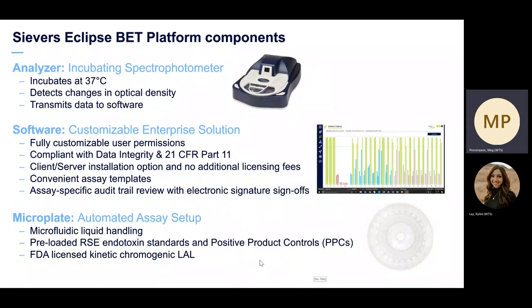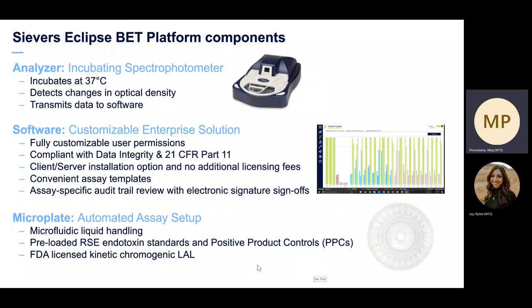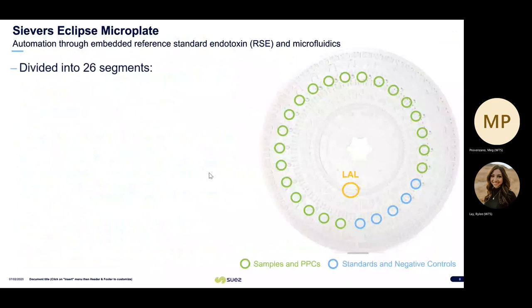There are also convenient assay templates. The microplate is a microfluidic liquid handling plate pre-loaded with RSE endotoxin standards and positive product controls. It can also use the FDA-licensed kinetic chromogenic LAL. The microplate allows for precise measurement, distribution, and mixing of samples, standards, and LAL. There's a one-to-one sample-to-lysate ratio, which maintains the same biochemistry as traditional microplate readers.